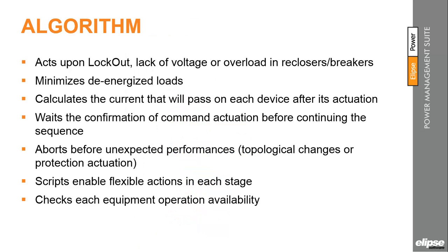And here we have how the self-healing algorithm works. To start, the trigger input for beginning is the signalization of either a lockout, lack of voltage, or overload in any equipment, be it reclosers or breakers. Lockout means that the recloser has exhausted all its attempts to restore the circuit. This often happens when there is a permanent fault on the network. While the lack of voltage indications helps to identify substation shutdowns and allows their respective loads to be transferred to another source, the overload monitoring ensures that the network stability won't be jeopardized by destabilizing events.